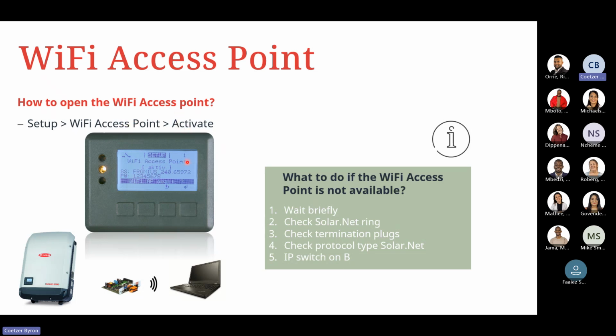So there are important notes to make when the Wi-Fi access point is not available. We always say to wait briefly. What happens is the unit will do a DATCOM check to make sure that the DATCOM is 100% before allowing you to open up the Wi-Fi access point. If it is not available, we always say check the SolarNet ring. This is in turn making sure your termination plugs are in place. Check the protocol is set to SolarNet and not interface on the unit itself, and make sure that the IP switch on the bottom of the data manager card is set to B and not A.